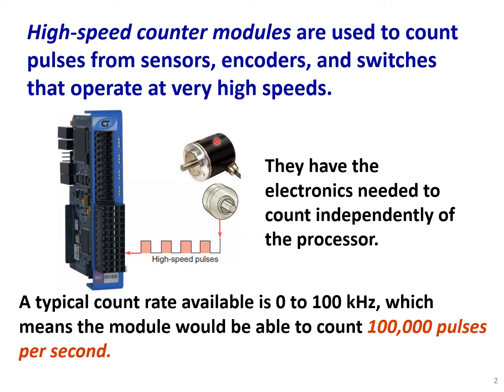Here we have our motor and the motor has a counter — usually a high-speed counter — which is basically a position sensor that sends the position of the motor to the PLC. These types of modules have the electronics needed to count independently of the processor, because you have a huge amount of input coming. A typical count rate available is 0 to 100 kilohertz, meaning the module can count 100,000 pulses per second. These are the pulses coming from encoders.